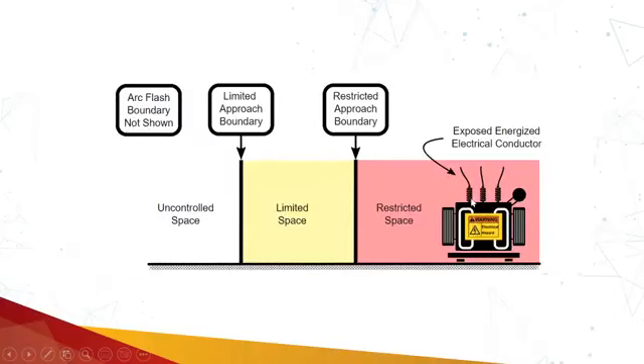So if we have a transformer room and it is energized, these are exposed energized conductors and circuit parts. So we are going to calculate the restricted approach boundary and the limited approach boundary. The limited approach boundary is basically a trigger that we have to keep unqualified persons away from. No unqualified person is allowed to enter the limited approach boundary unless there is an emergency, or he has to enter in order to pass or cross, not to perform any job there. He should be escorted by the qualified person.